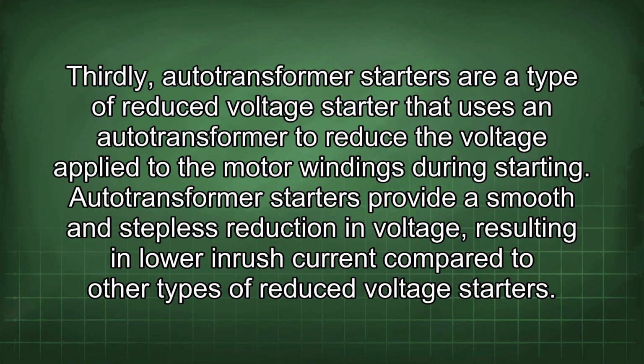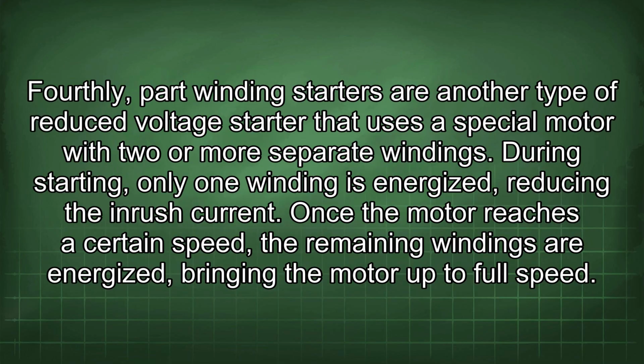Thirdly, auto-transformer starters are a type of reduced voltage starter that uses an auto-transformer to reduce the voltage applied to the motor windings during starting. Auto-transformer starters provide a smooth and stepless reduction in voltage, resulting in lower inrush current compared to other types of reduced voltage starters.